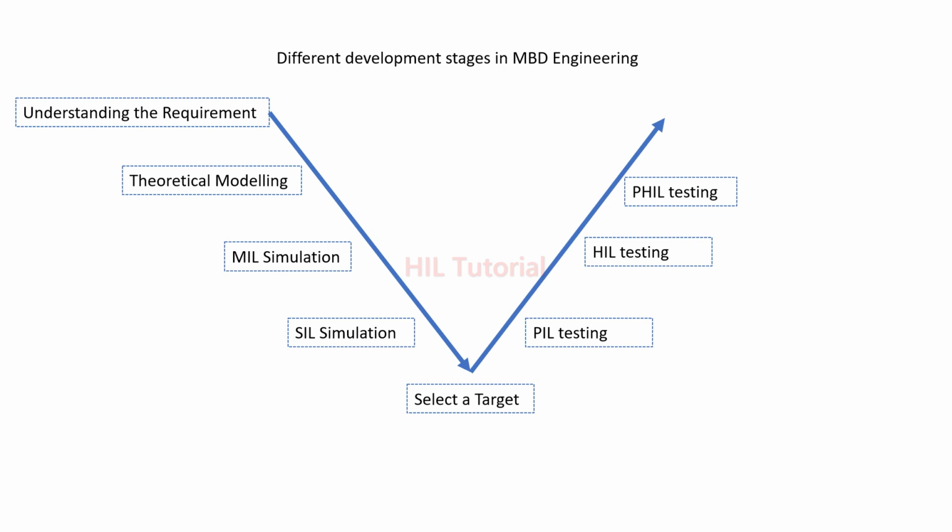In this stage things are not easy, it is a very complicated stage, because your plant or controller may be in the real-time hardware, and some part of your test will be in the physical world. So in between you have to put something: a power amplifier will take place, and that will interact between the model available in the real-time simulator and the physical model. So it is a little bit difficult testing stage, but some people do it.